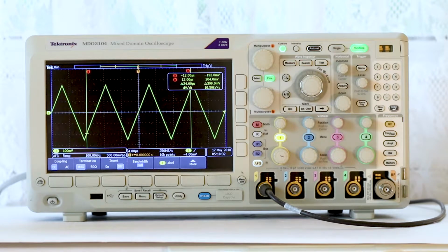There are approximately 20 items that appear in the time domain display. However, they do not all appear at the same time. Starting at the upper left, just after the Tek logo, is the run-stop indicator. At a glance, you can tell whether the acquisition is running or stopped. This condition is determined by pressing the run, stop, and single acquisition buttons.